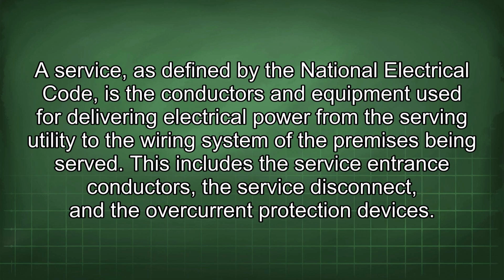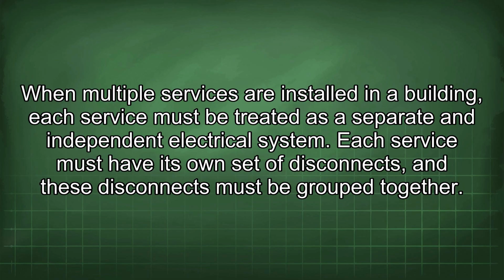A service, as defined by the National Electrical Code, is the conductors and equipment used for delivering electrical power from the serving utility to the wiring system of the premises being served. This includes the service entrance conductors, the service disconnect, and the overcurrent protection devices. When multiple services are installed in a building, each service must be treated as a separate and independent electrical system. Each service must have its own set of disconnects, and these disconnects must be grouped together.